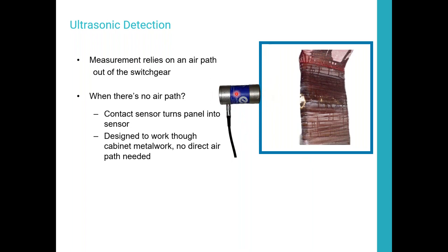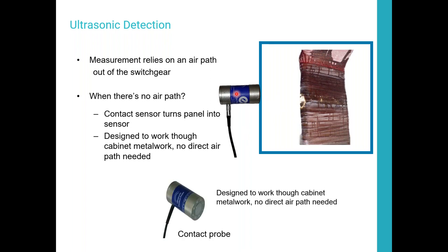So you've got these contact sensors, which are extremely sensitive ultrasonic microphones that are designed to be attached to the metal. It's got a microphone disc in the middle here that's extremely sensitive, and they're designed to listen through the metal for the ultrasonic activity inside the gear. So basically, it's a way to detect surface discharge without having to de-energize your equipment.